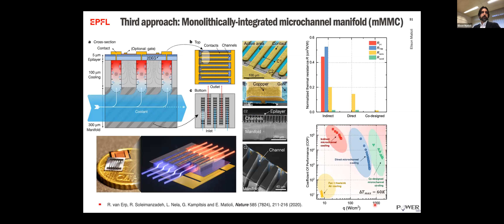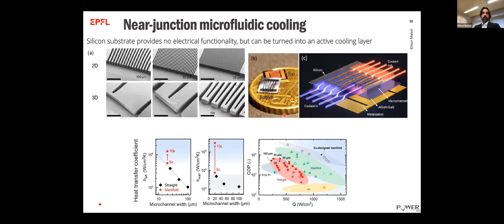And when you look at the thermal resistances between these three different approaches, you can see the massive reduction that you can have when you go from the indirect to this co-designed approach. So in the indirect approach, we had the junction to case, thermal interface material, convective and conductive terms, which basically got completely eliminated by putting the microfluidic channels in close proximity with the gallium nitride. So by doing that, we can now achieve very high coefficient of performance, which is basically the efficiency of the cooling, while extracting heat fluxes of 2 kilowatts per centimeter square. Of course, we optimized everything. We optimized the micro channel itself. We optimized the distribution network that we made to achieve this high performance. And here I'd like to show how this works.